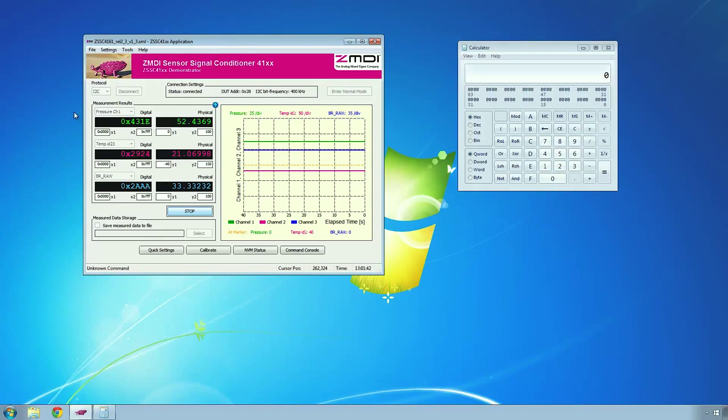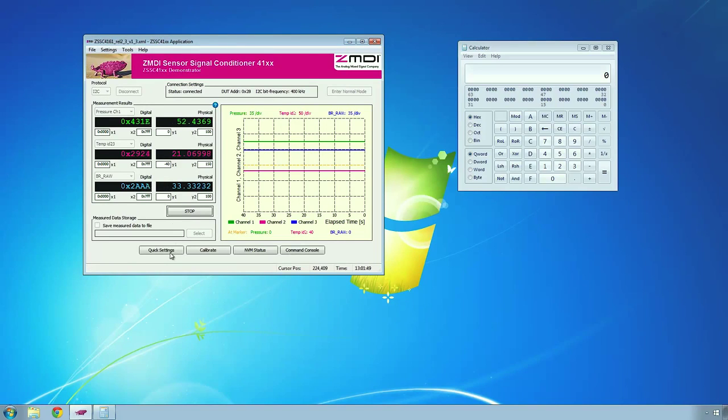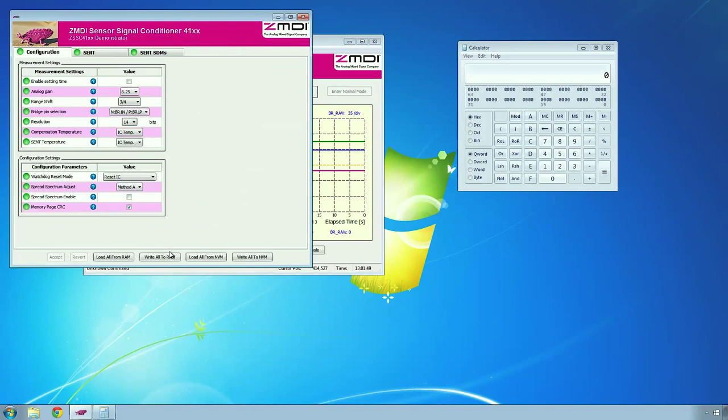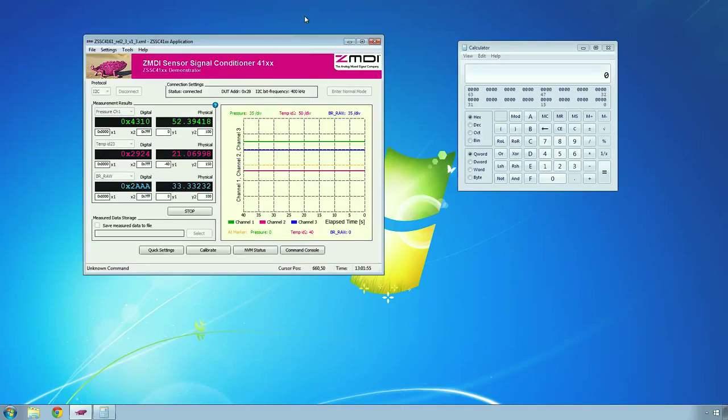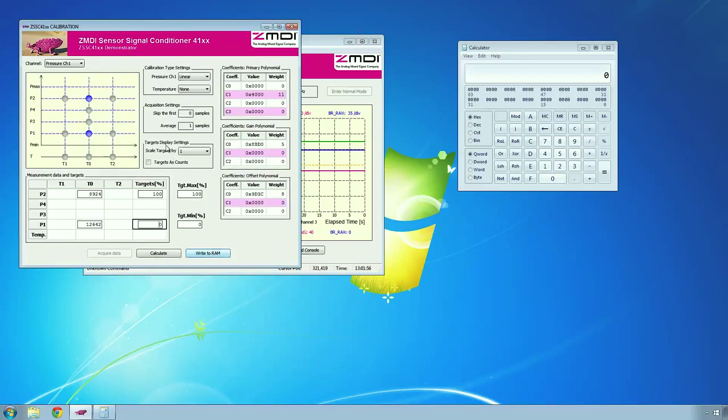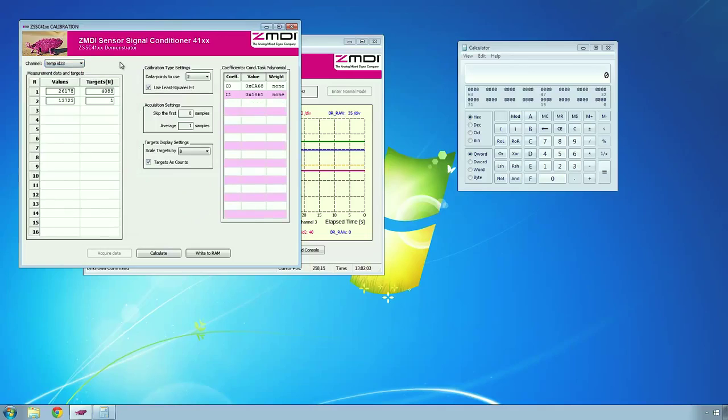On the software side, the first time you'll come in and load an XML file, and that will load in some basic parameters. You can check those in the quick settings, and then load those into RAM, write all to RAM. Then you'll want to come in here and calibrate your sensors. I've already done that for both the pressure and temperature sensor, so those are good to go. I've already written those out.